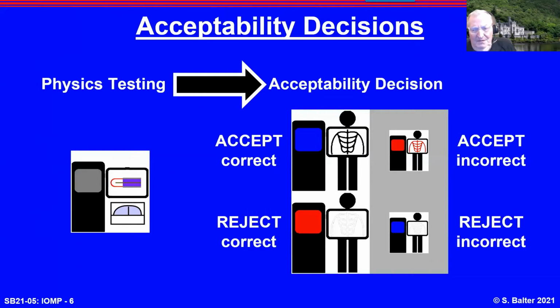Basically, there are 4 possible decisions. You accept the equipment is working correctly and you go on and use it. You reject the equipment because it's unsafe or poorly performing, and this is correct. You also may accept poorly performing equipment, which can physically damage the patient in one of a number of ways. You can also incorrectly reject perfectly acceptable equipment, which may have consequences if alternate equipment is not available.